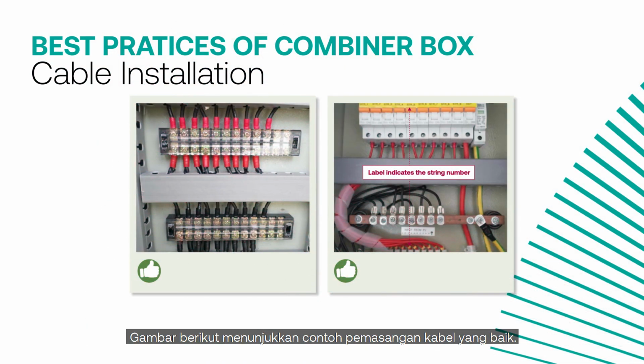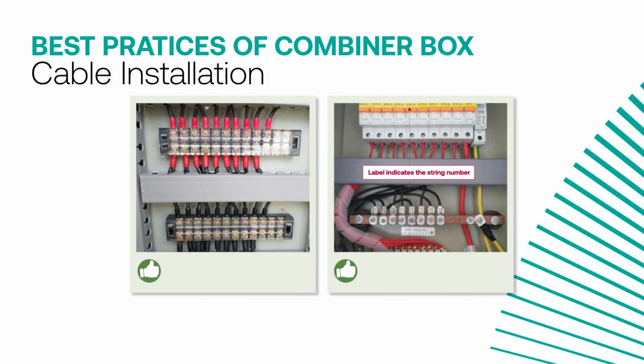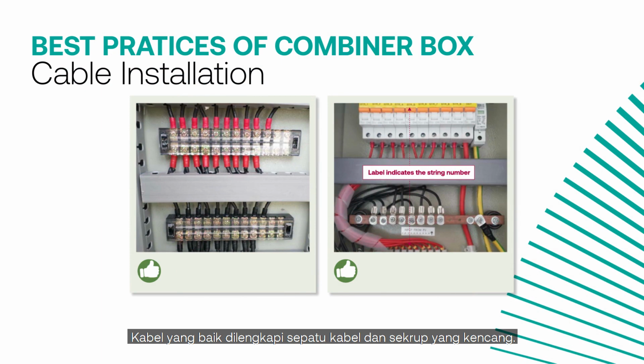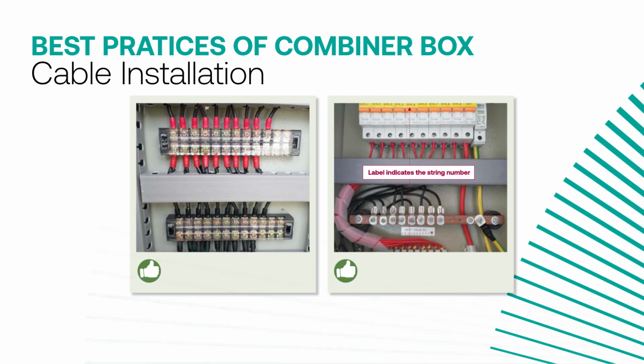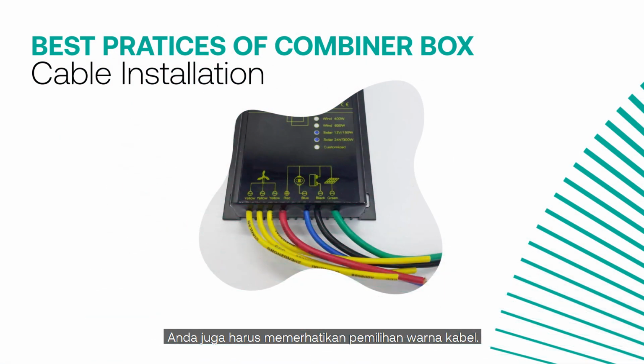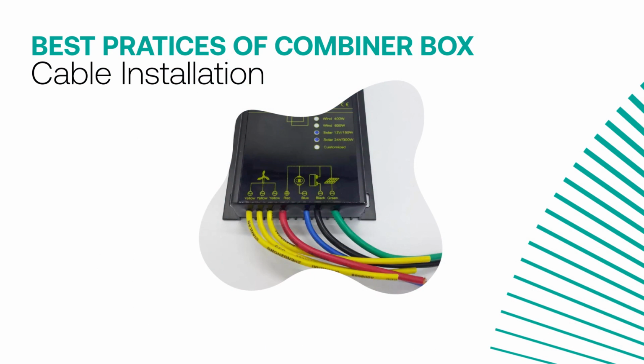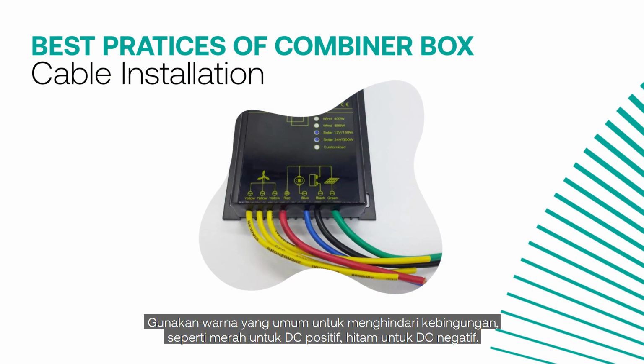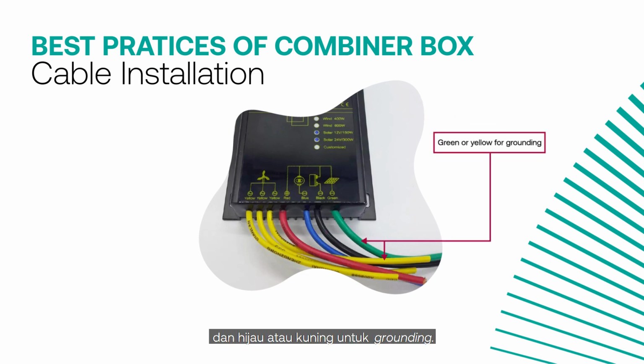The pictures show good examples of cable installation. Cables are well equipped with cable shoes and screws are properly fastened. MCBs and cables are labeled and correctly colored. This helps the technicians when tracing problems. You should also pay attention to picking the cable color. Use a common cable color to avoid confusion as follows: red for positive DC, black for DC negative, and green or yellow for grounding.